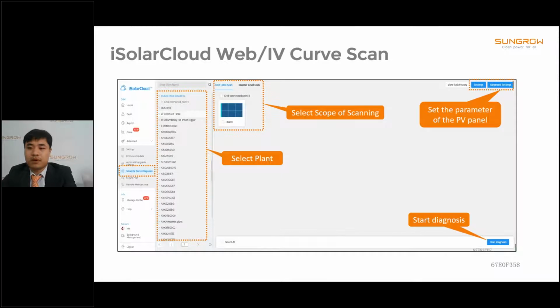We can have an overview of our added-on feature, IV curve scan. It's able to find out shielding, dusting, errors like short circuit of the PV modules, diagnose strings, and output graphical reports with suggestions, just with one button start. It's also easy to operate via iSolarCloud.